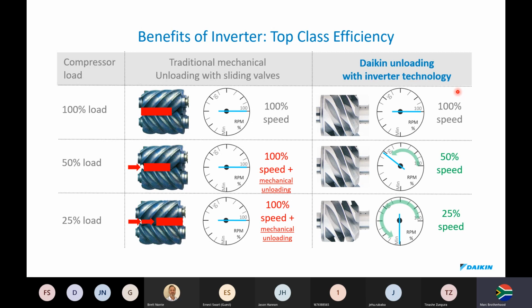Now, if we look at Daikin's unloading technology, when we need to unload as the load drops, we have a single screw. Notice these are twin screws, which Daikin don't use. They're very noisy, high maintenance because of all the wear metals, with up to 6 times more bearings compared to our technology. So we use a single screw, and as we unload, we slow the compressor down.